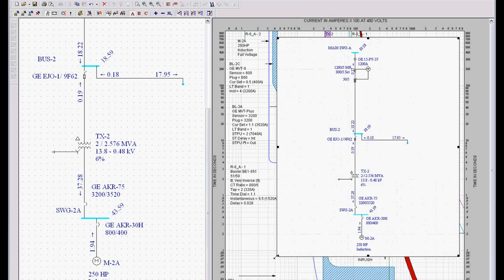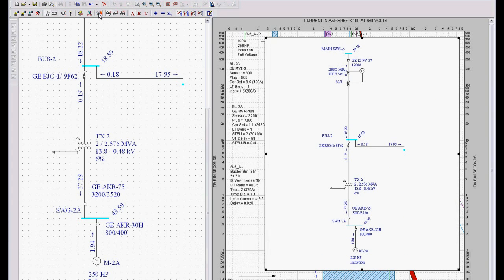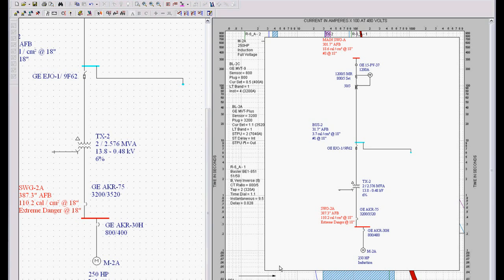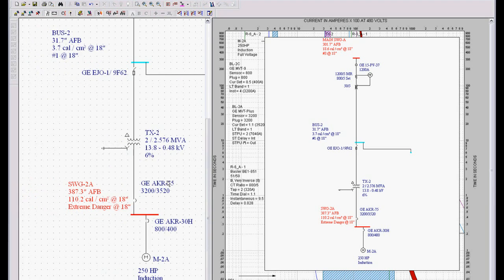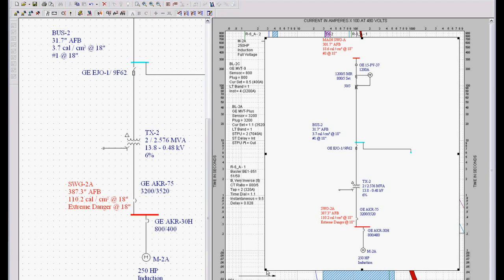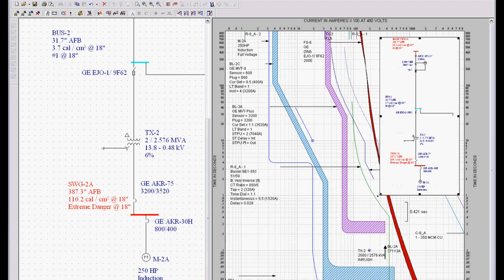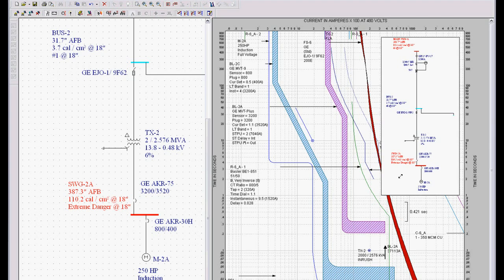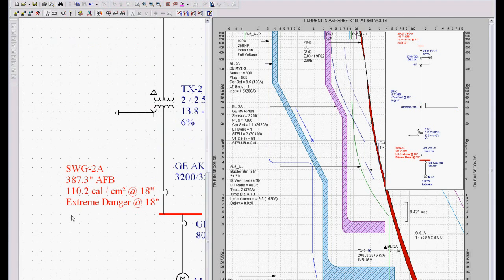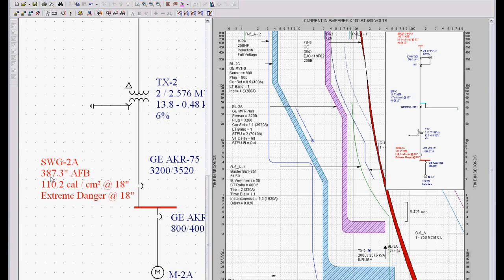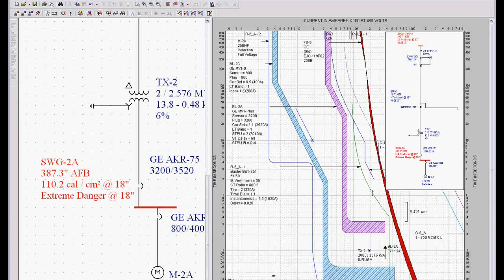Even to the point if I want to go and add ArcFlash, here's my ArcFlash values. So you can have time current curves for ArcFlash, you can have time current curves showing the protective device settings. And they can all be saved and printed. So that's the really cool thing. Since we're here, let's get into ArcFlash a little bit. Now, look what happens. In this case, I have 110 calories of energy. I'm actually using the worst case calculation right now. 110 calories of energy, a 387 inch ArcFlash boundary, extreme danger. Look what happens as I change the curves.